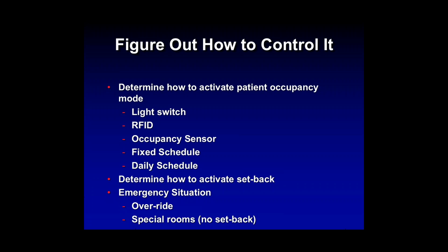We considered RFID tags on the patient so that when you rolled them in, it would sense that and kick up to 20. Occupancy sensors, so make sure that you have a redundant group of sensors that if anybody even twitched in the OR, it would pick that up and make sure that it maintains the 20 air changes. Also, a fixed schedule, which will work just fine in an ambulatory surgery center when all the cases basically start at 7 a.m. and the majority of them end at 3:30 or 4:30. You can just make sure that you put a buffer on the end of that and you'll be covered. Or looking at a flexible daily schedule.